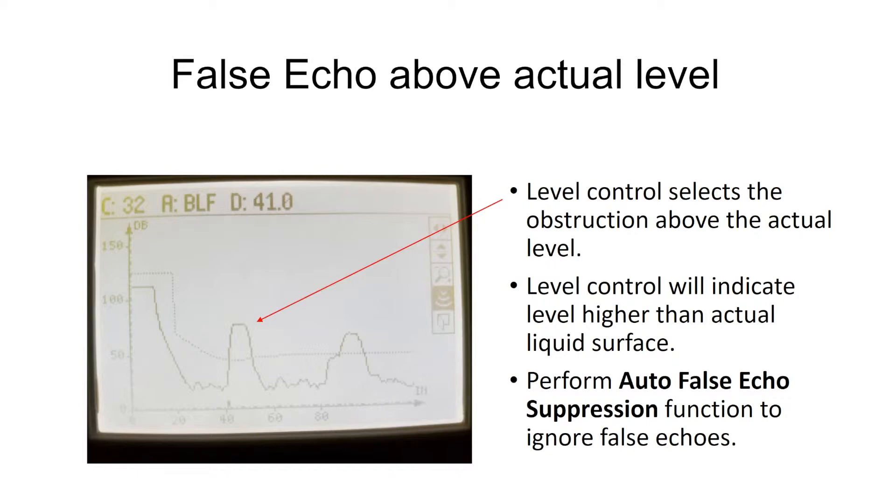We have a couple of options. Number one is, if we have the sensor right above a very reflective device, whether it be a wall or a pipe, if we consider moving it to get rid of that obstruction, that's probably our first choice. If not, there's some tricks we can do. One of them is the auto false echo suppression. What that does is it basically maps out any type of false obstruction we have above the actual level. That works pretty well, but does not work all the time.